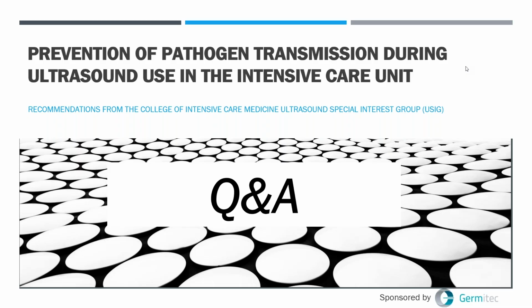Okay, just a comment here: the recommendations are closely aligned with the findings of the UK Committee on Reprocessing of RMDs. They also have a question: are you expecting an instrument-grade disinfectant to be used on the high-frequency portion of the machine, or is a hospital-grade sporicidal being recommended? So if a device is not a reusable medical device, you can use a lower grade of disinfectant.